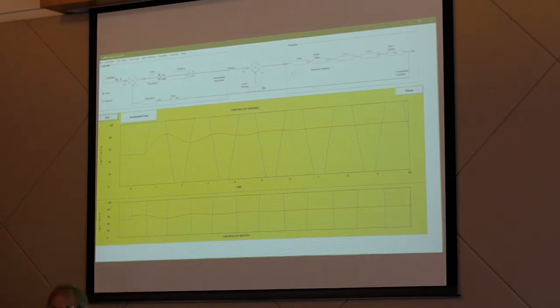Yeah. We always had rules of thumb for proportional band. When we set up receiver controllers, we would make sure the proportional band was somewhere between 15 and 18%, so that we weren't too much or too small. Yeah, but if you're going for perfection, what you actually do is keep narrowing that down until you start to see the loop go unstable. And what you just discovered is the safe side of this zigzag. And so then you say, okay, that's where I'm going to stop, and I'm maybe going to go back the other way a little bit.